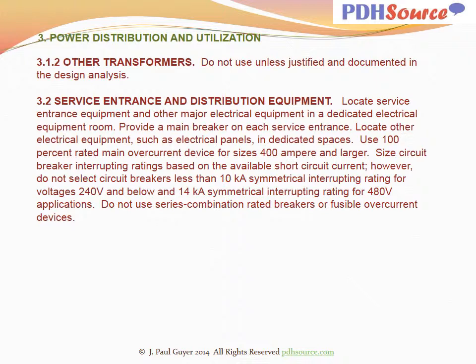Use 100% rated main overcurrent device for sizes 400 amperes and larger. Size circuit breaker interrupting ratings based on the available short circuit current. However, do not select circuit breakers less than 10 kiloamps symmetrical interrupting rating for voltages 240 volts and below, and 14 kiloamps symmetrical interrupting rating for 480 volt applications. Do not use series combination rated breakers or fusible overcurrent devices.